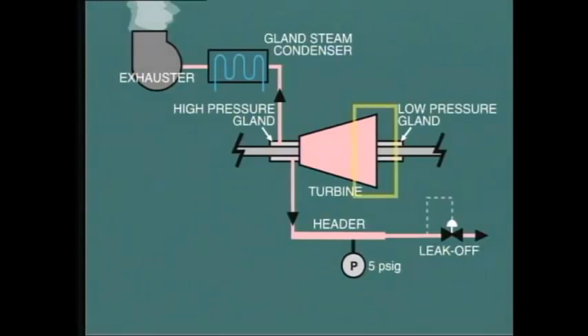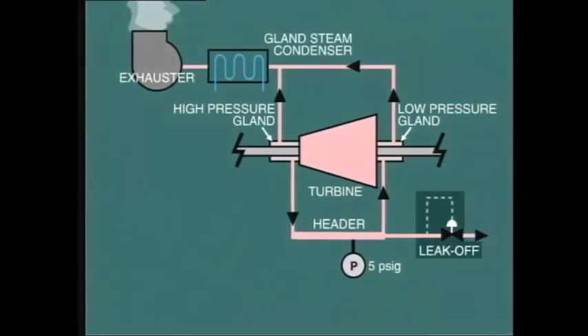Now let's see what's happening at the vacuum end of the turbine. Well, we definitely do not want air to enter the casing, even the small amount that may flow across the labyrinth seal. In order to prevent the leakage of air into the casing, low-pressure steam is provided from the header to the low-pressure gland seal. This results in a small amount of steam entering the turbine casing, and this is far preferable to air. Of course, some of the steam will also try to pass along the shaft in the opposite direction to atmosphere. But this is captured by the gland steam exhauster in the same manner as for the high-pressure gland seal. So we can see that leak-off steam from the high-pressure end is useful in providing sealing steam at the low-pressure end. As the load changes, the leak-off valve opening adjusts to maintain the appropriate header pressure.